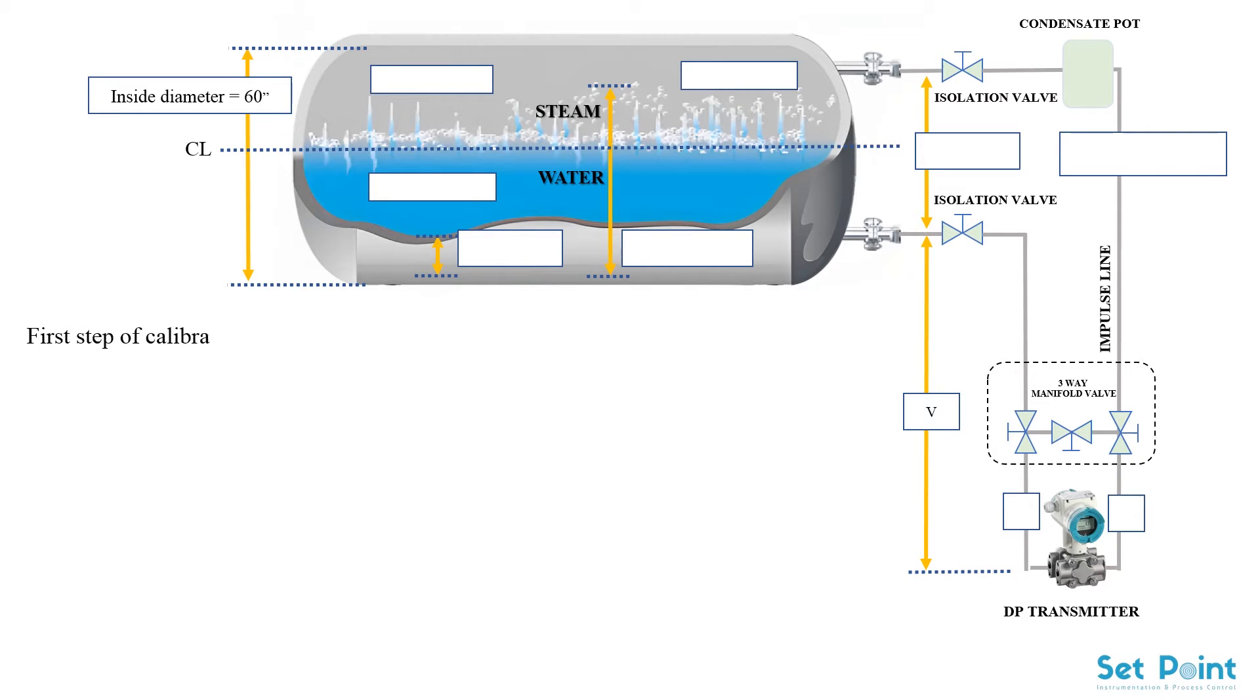First step of calibration is to define the process variables. So in this example we assume that the static pressure in the boiler drum and at the top tap is 2425 pounds per square inch gauge.